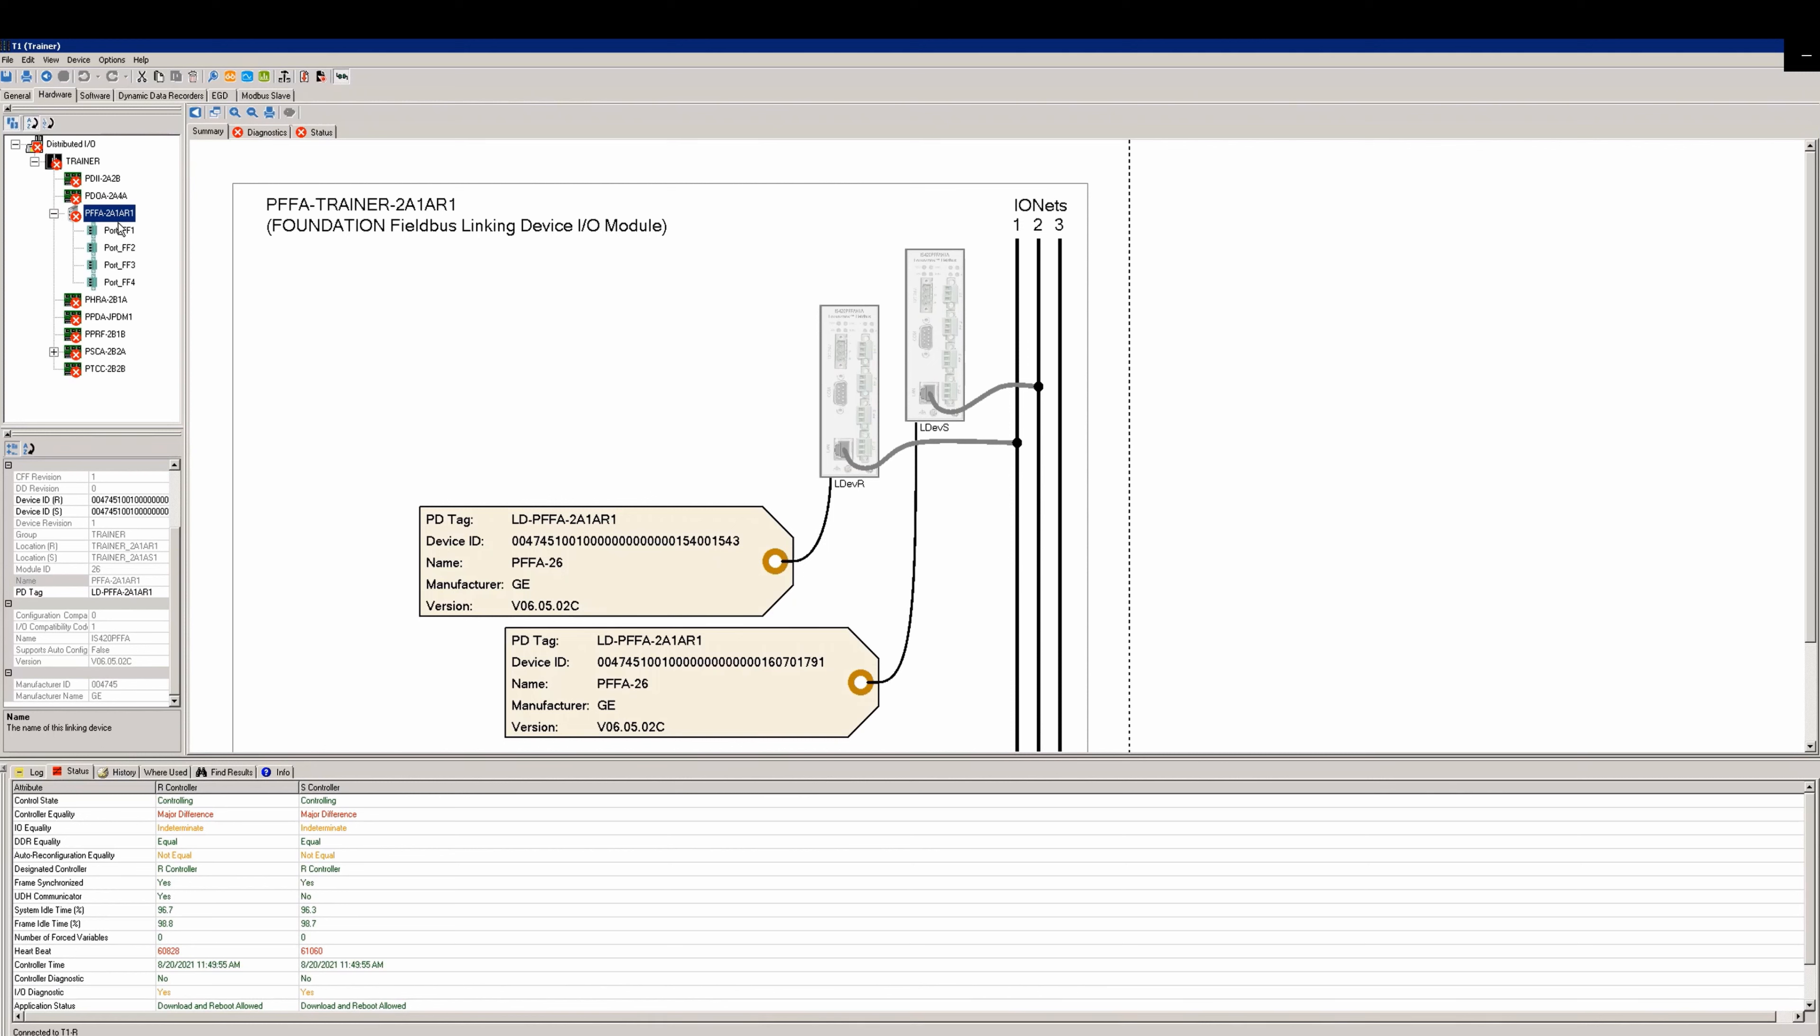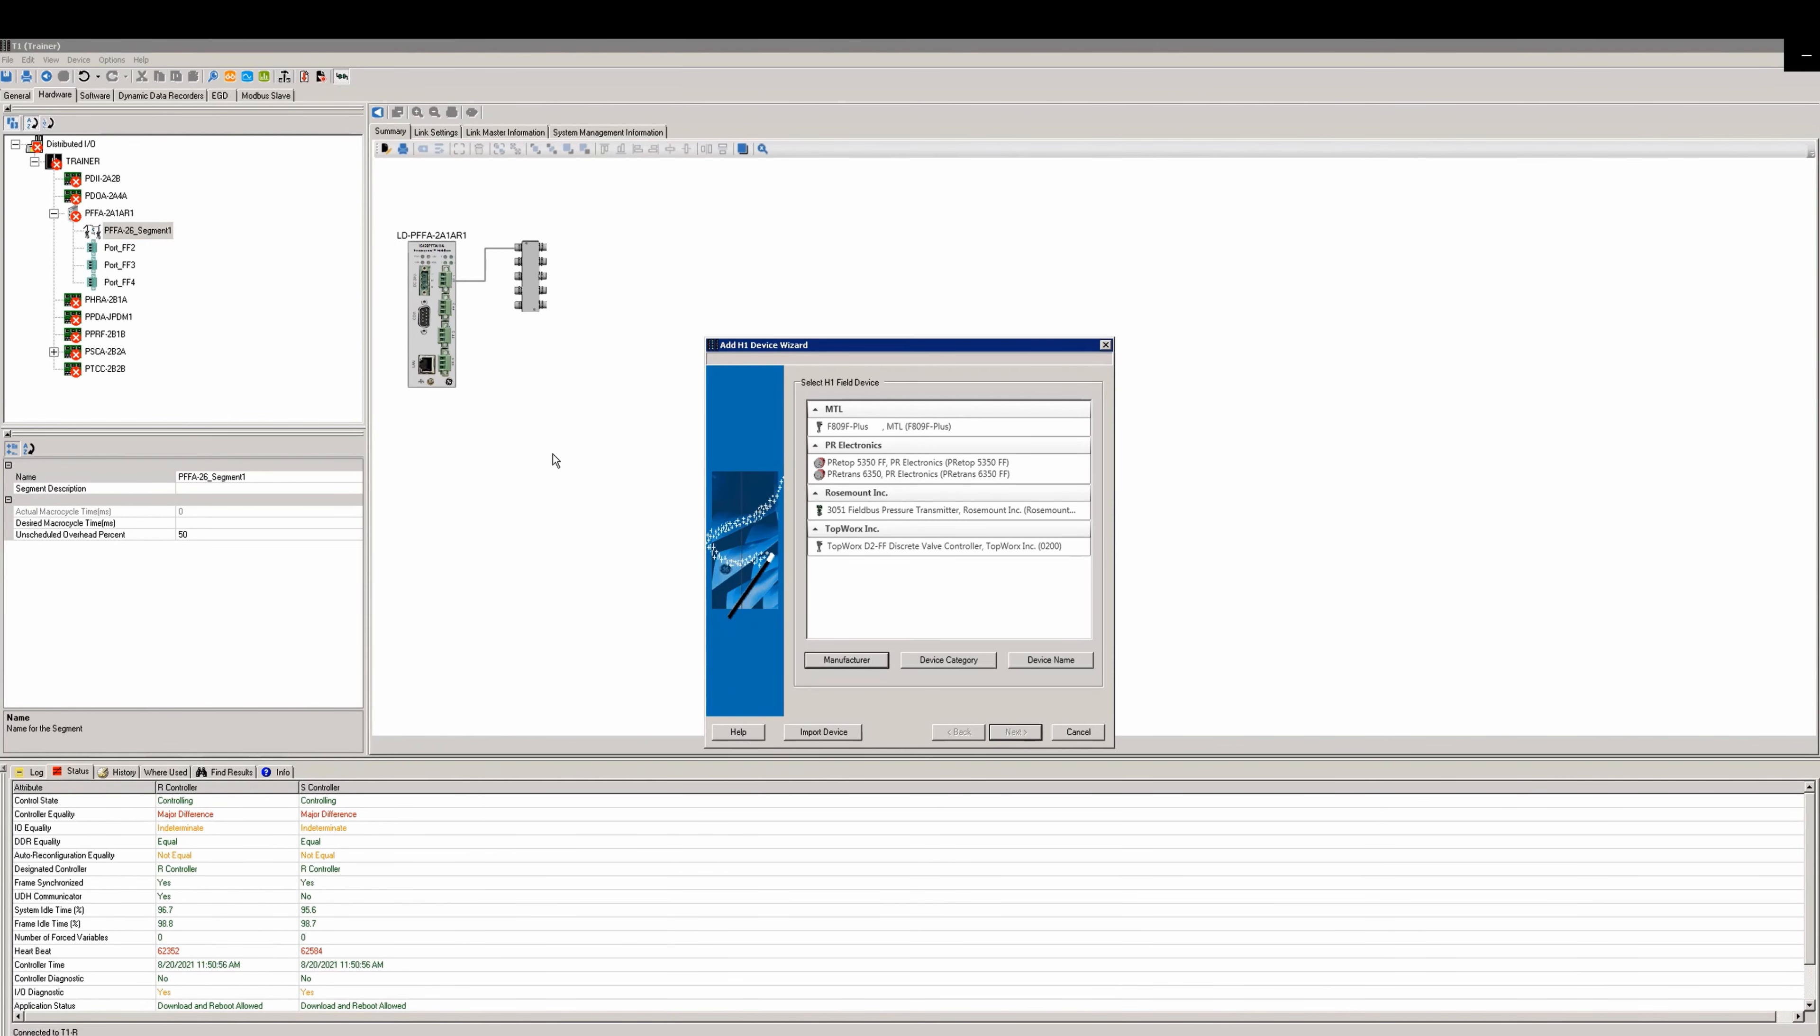Next you will need to add a segment and a device. Expand the tree under the new PFFA card you've added and select the segment where you want to add the device. In this case we're going to do it on the first segment. Right-click and attach segment, then right-click on the segment and select add H1 field device.